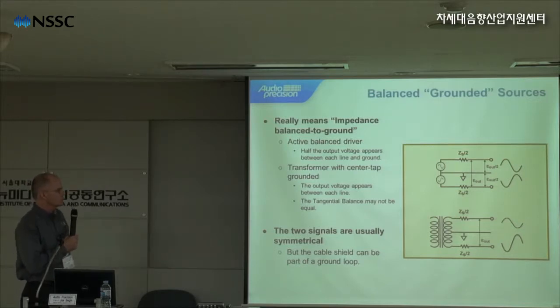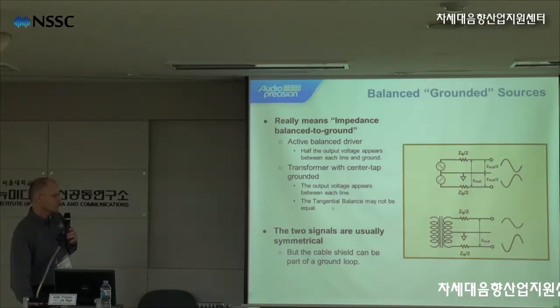For balanced grounded sources, this really means that the impedance is balanced to ground. We have an active balance driver, such as in the APX family, where half the output voltage appears between each line and ground. So the source impedance over 2 is in each of the two differential signal chains. Our older instruments use a transformer with center tap grounded, like our 2722 series, and that would correspond to the circuit diagram over here. In this case, the output voltage appears between each line and ground, and the impedance balance may not be equal.